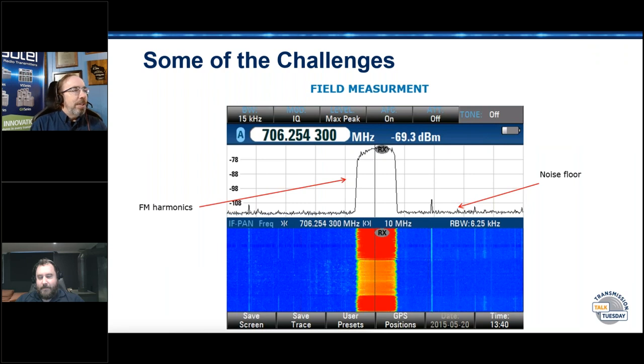So here's an example of an LTE interference complaint. This one goes back - you can see the date stamp, and that's accurate - it was 7 or 8 years ago. They're measuring and complaining about the harmonic being 70 dB down, and you can see they've got no attenuation set. They were using an antenna tuned for 900 megahertz, doing no fundamental attenuation whatsoever. So at that point, you have no idea what the reading actually is.